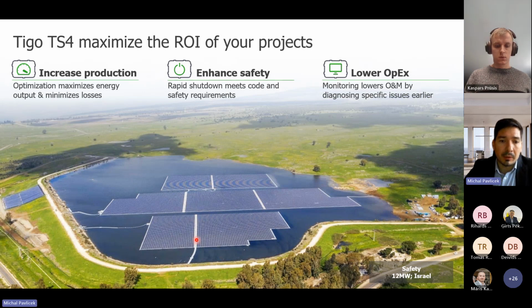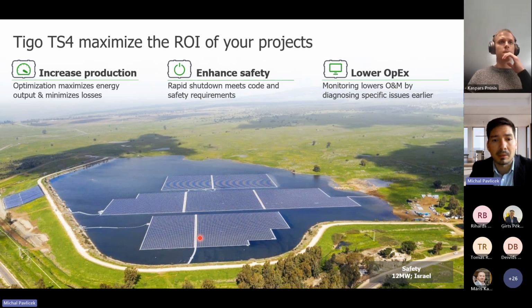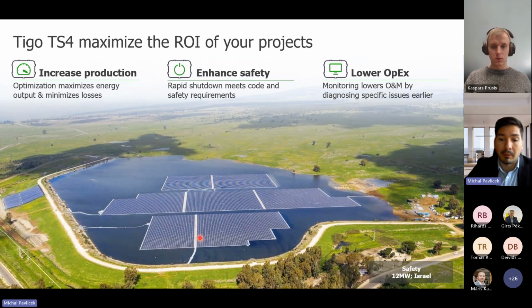So that's, of course, maybe extreme, but you may apply the same also on commercial buildings, where maybe you need to do a service during the rainy days. You can activate it. Or maybe you would like to do a service of only a single section of the project. So instead of switching off 1 megawatt to be in safe operation when you do service, you can, for instance, switch off just one segment, maybe 50 kilowatt. And if you would do a service of such a project for 2 days, and you avoid switching off, let me say, 950 kilowatt out of 1 megawatt, in fact, the 2 days out of operation will already pay all the investment that you have. So it's not costly, it's pretty cheap compared to the energy losses that it's avoiding. And typically the return of costs is very, very fast for these electronics.